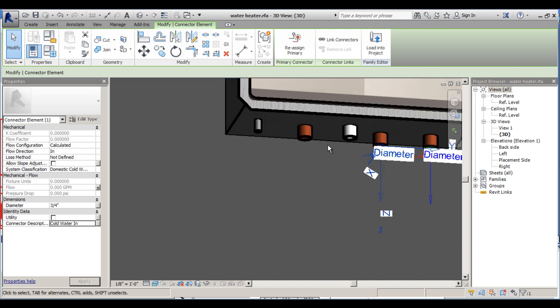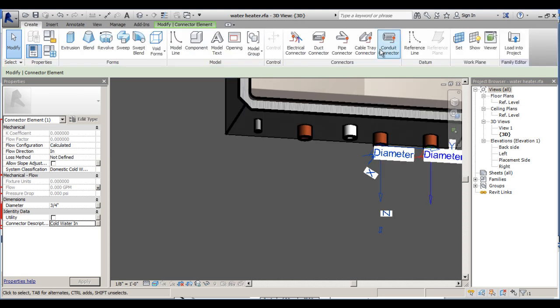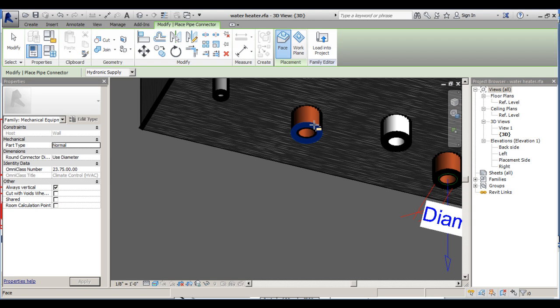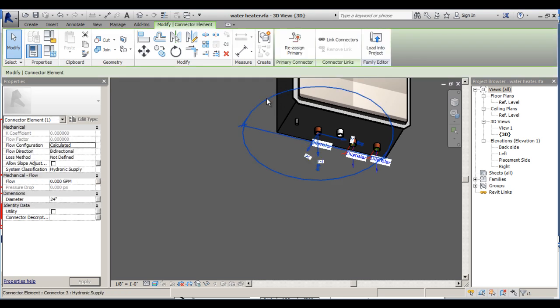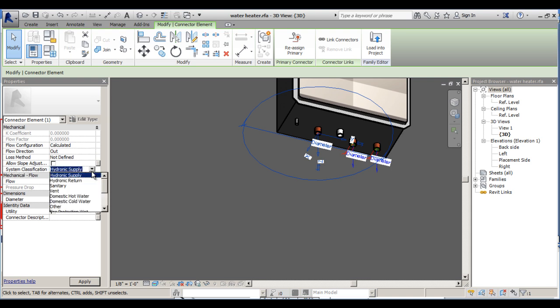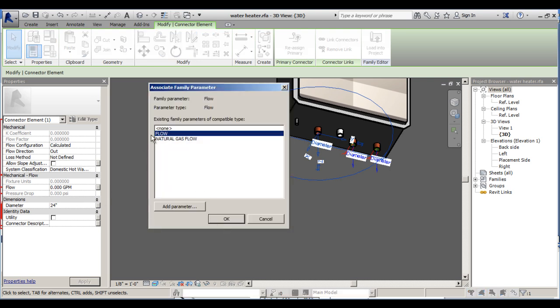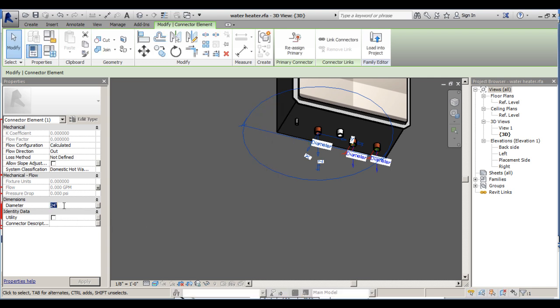We now have two connectors set up — gas in and cold water in. Now let's model our connector for hot water out. Go back to Create, choose pipe connector, make sure we're on face, and click the bottom part of our extrusion again. Select the connector: flow configuration is calculated, flow direction is out, loss method not defined, system classification is domestic hot water. We'll associate the flow parameter shared between hot and cold water. Diameter is three-quarter inch.